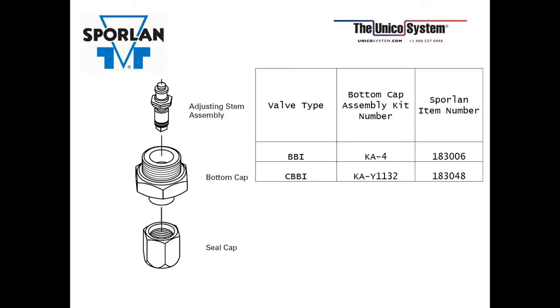So you need to get yourself a bottom cap assembly kit from your local wholesaler. And these two, BBI and CBBI, are the two most common that Unico uses. So those parts, the KA4 and the KAY1132, are what you're going to need. And you're going to basically convert your non-adjustable valve to an adjustable valve. So when you get back together and you take your good superheat reading, you can now adjust it if you need to.